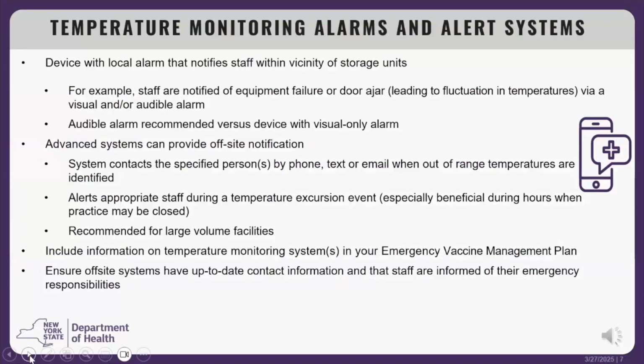The simplest type of alert systems are temperature monitoring devices that notify persons that are in the vicinity of the storage units if there is a problem, such as equipment failure or the door was left ajar. These local systems alert staff via a visual or audible alarm on the device, or both. More advanced off-site notification systems are useful after office hours to notify one or more staff persons in the case of a temperature excursion. These systems can be set up with a primary contact as well as backup staff. The contacts may be the vaccine coordinators or the medical director, and would receive a telephone call or other type of notification such as email or text in the event of a temperature excursion.